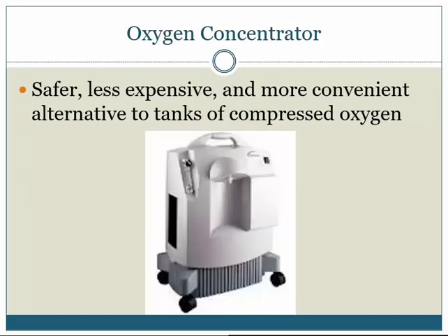Another common way you'll see oxygen delivered in the sleep lab is with a concentrator. Basically, it pulls in room air and concentrates the oxygen in room air to deliver it to the patient. It's a lot more convenient. They are safer and less expensive than tanks. But you are limited with the maximum liter flow that can be delivered. Typically these things max out at 4 or 6 liters per minute. The other thing too is they're loud and they can really heat up a room.